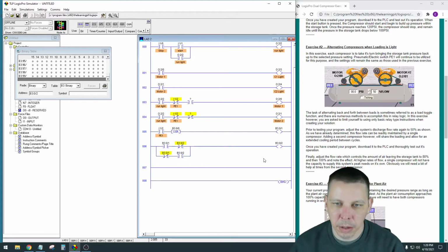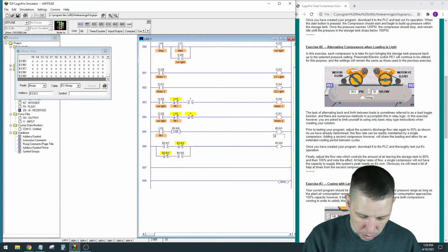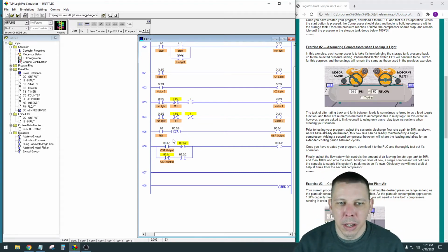So before I check it, let me just label this. I'm going to call this the OSR. One-shot rising is what OSR stands for. This is the output associated with that one-shot rising. That's the word I was trying to think of earlier. It needs a memory location in it so it knows if the scan that it's currently on is on the rising edge, meaning it went from false to true just in this scan.